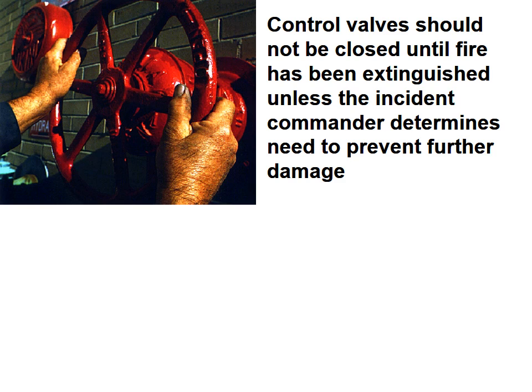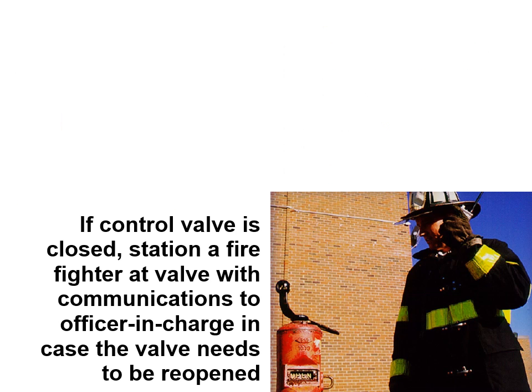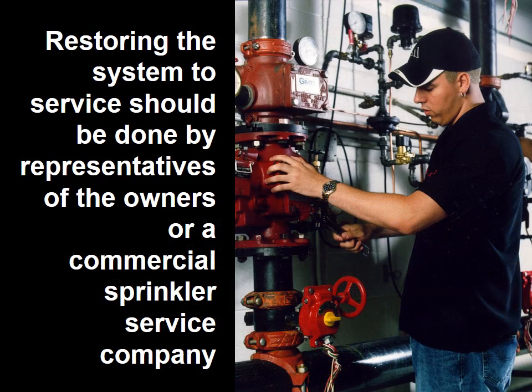The control valve should not be closed until the fire has been extinguished, unless the incident commander determines the need to prevent further damage. If the control valve is closed, station a firefighter at the valve with communications to the officer in charge in case the valve needs to be reopened. Restoring the system to service should be done by representatives of the owners or a commercial sprinkler service company.